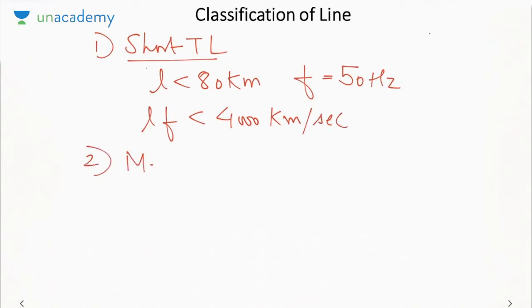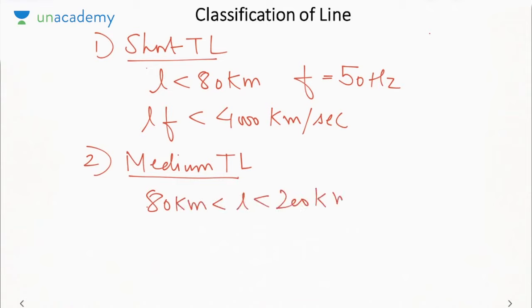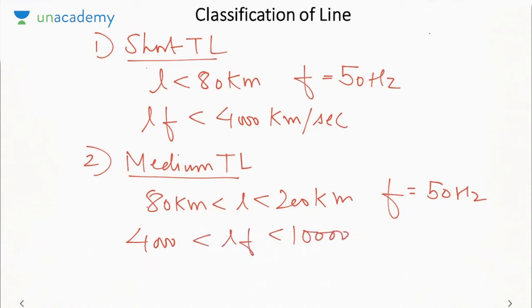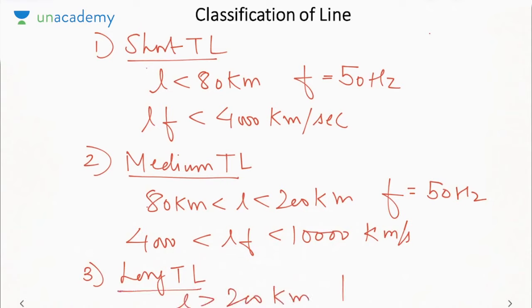Next we define the medium transmission line. Length will lie between 80 km and 200 km for a frequency of 50 Hz. So what will be the product of LF? 4000 up to 10,000 km per second. Next we define the long transmission line, where L is greater than 200 km for a frequency of 50 Hz. So LF is greater than 10,000.